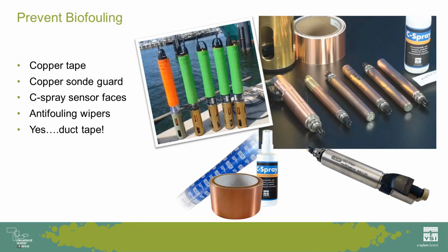We have a lot of users that cover the body of the sonde with duct tape, and that's really handy, particularly in marine environments, because instead of trying to chip all those barnacles off, you can just break into that tape and cut it off.